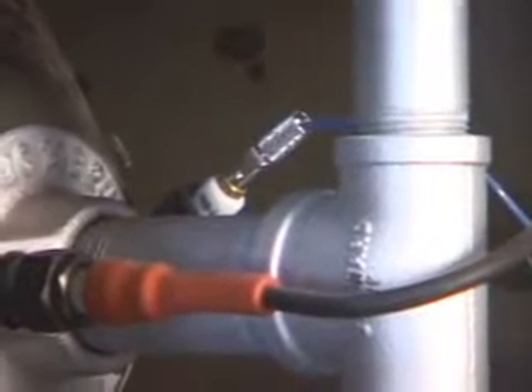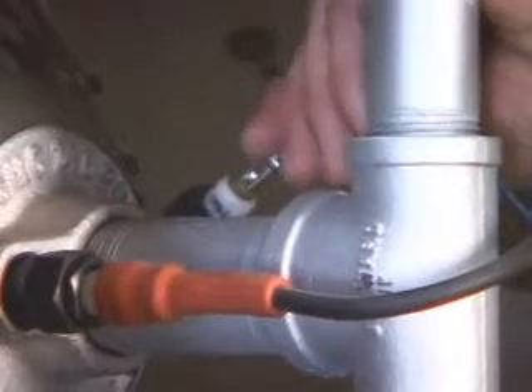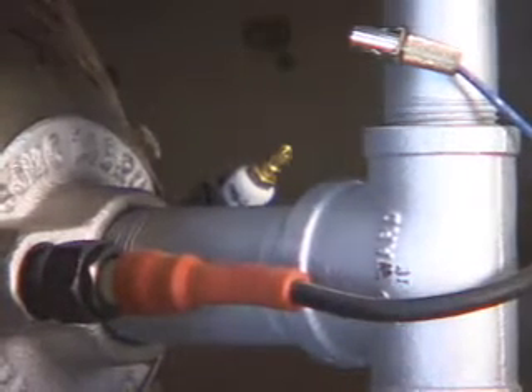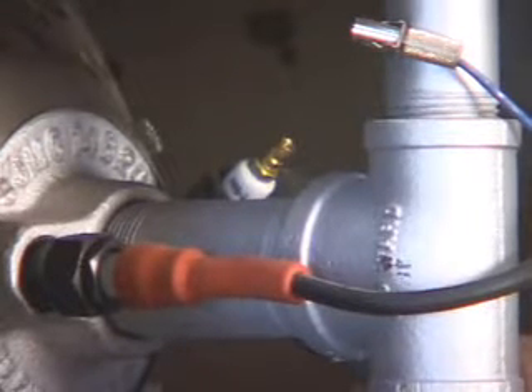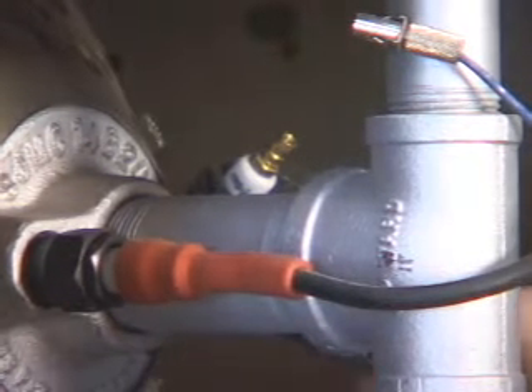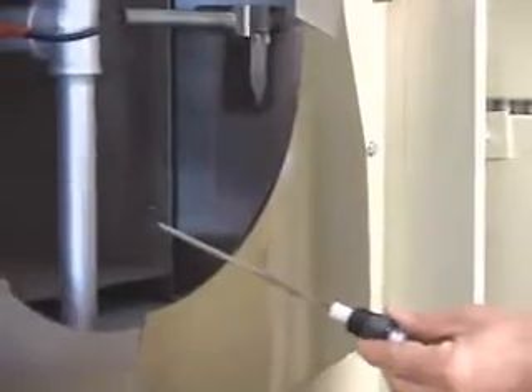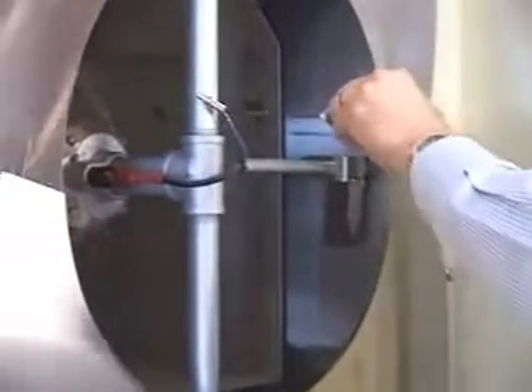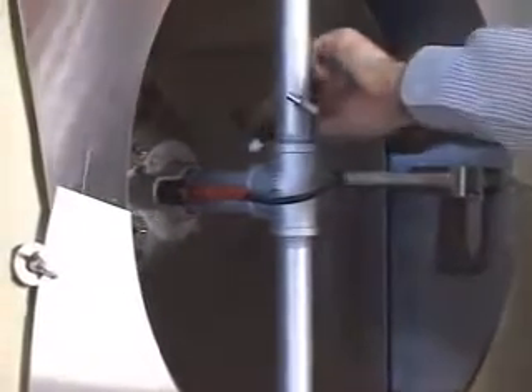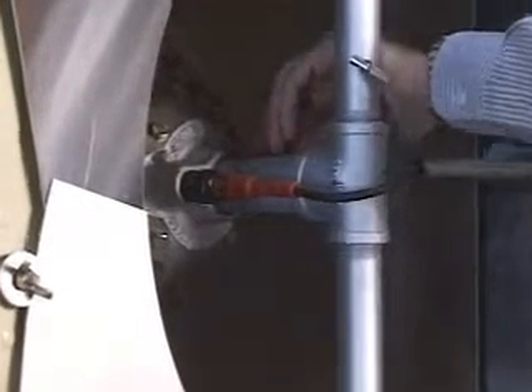The spark plug and flame electrode will need occasional cleaning and inspection, especially if running on propane. Ensure that power is turned off before disconnecting these wires. Use a screwdriver or pocket knife to gently scrape accumulations off the flame rod. A wire brush will work well to clean carbon from the end of the spark plug. We strongly recommend applying high-temperature never-seize compound to the threads before replacing.